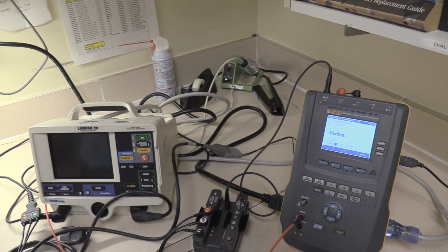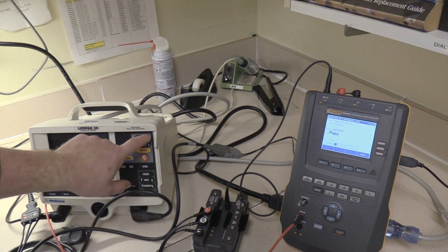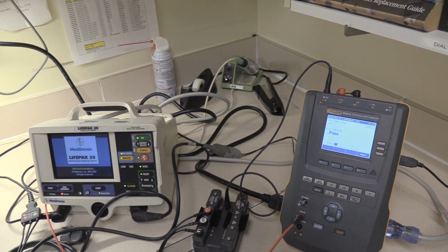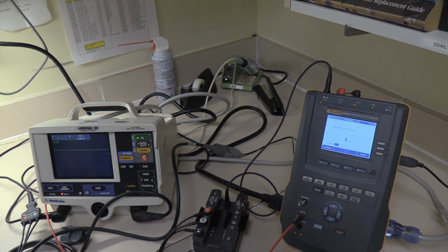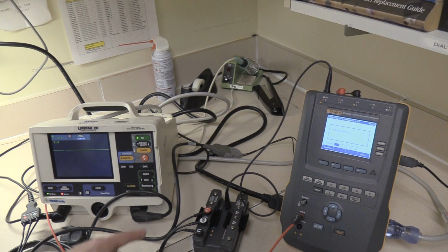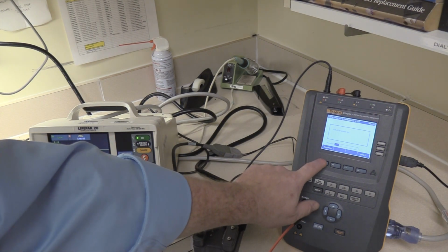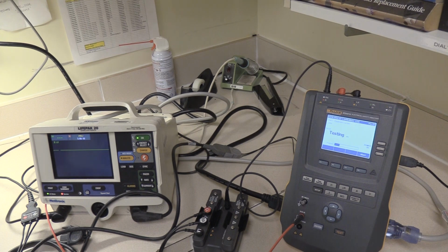And we're going to go through and check the ground wire resistance with the defibrillator powered off. And we can power it on here now at the end of that test. Or remember, since we had a pause at the power on, it'll tell us when to power on the defibrillator. Right here, it tells us to power it on. We've already powered ours on. And so we're going to go ahead and press continue. F1 to resume the test.